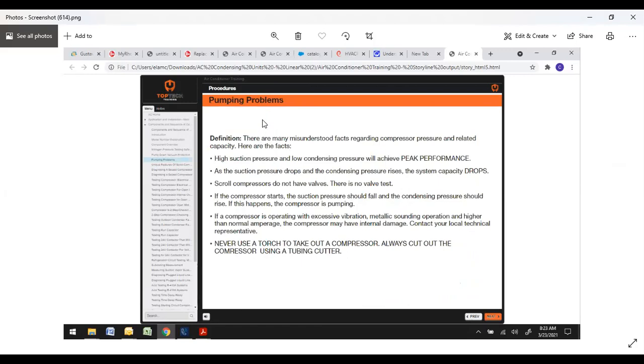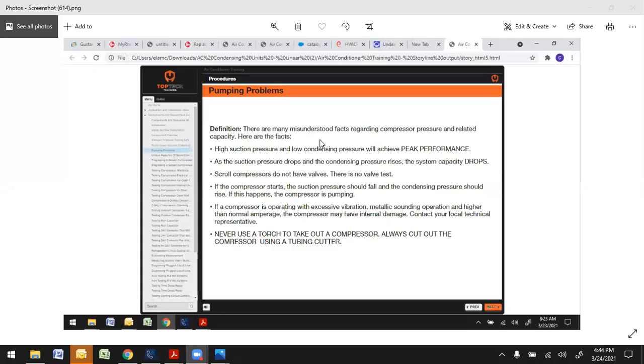So, compressor pumping issues. Okay. There are many misunderstood facts regarding compressor pressure related capacity. High suction pressure and low condensing pressure will achieve peak performance. As the suction pressure drops and your condensing pressure rises, the system capacity drops.